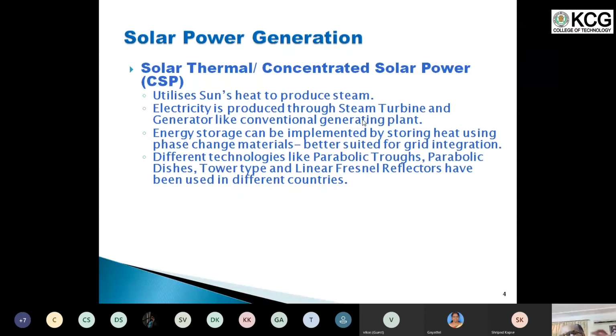I implemented a 2.5 megawatt developmental project in Bikaner in the year 2009-10, using roughly 1 square meter mirrors, about 4,000 mirrors for the 2.5 megawatt plant. These mirrors track the sun and are called heliostats. The heliostats track the sun and can move on two axes. The main technology here is the heliostat tracking the sun, and we had gotten into a collaboration with a firm from the US to implement this 2.5 megawatt plant, but there were problems.